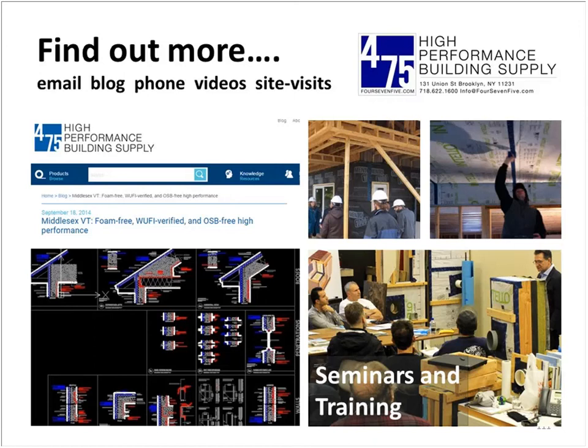Sure. Just again, the basic issue is what we need to look at. It's very climate specific as we move from the mixed climates to hot and humid in particular. What the vapor dynamics are moving through the enclosure. Generally speaking, when we are in truly hot and humid, we're looking at vapor retarding outboard, airtight outboard. So we're keeping the hot and humid air of the environment out of the insulated enclosure, because now we're pretty much over air conditioning these buildings, right? We've got essentially a refrigerator going in a hot and humid environment. So that risk, that moisture risk in the enclosure is flipped.